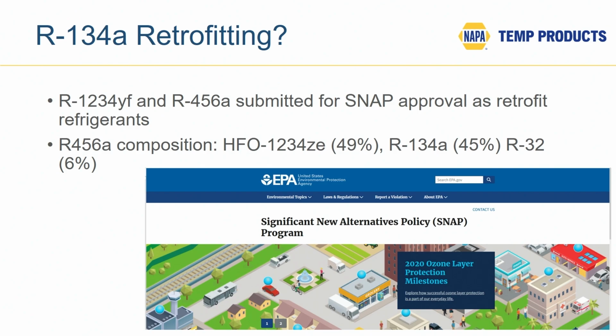There is another product called R456A. It's a blend of three refrigerants: 1234ZE, not YF, ZE, about 49%, 134a at 45%, and another refrigerant called R32 at 6%. And that has also been submitted to the EPA for approval to use as a retrofit refrigerant in older R134a systems. I'm not so sure. Certainly the advantage of that product is that you could top off. The expectation is that because a significant amount of it is R134a, you could top off an existing R134a system with this blend refrigerant. But that's what's going on at the moment.